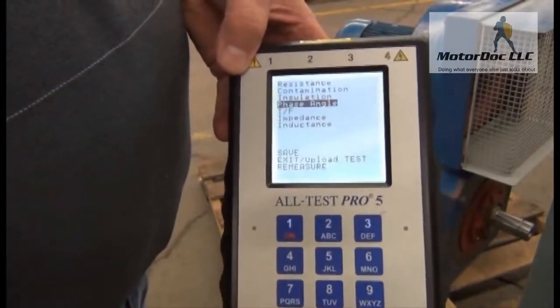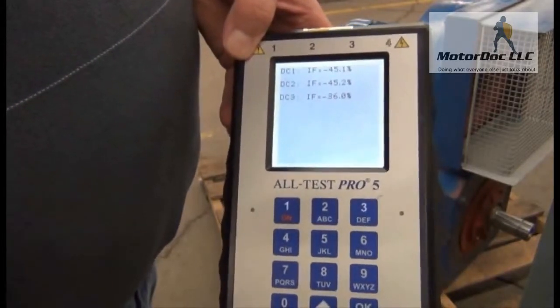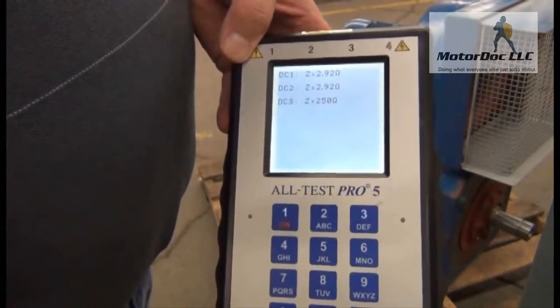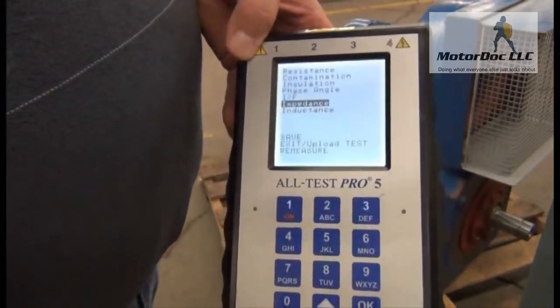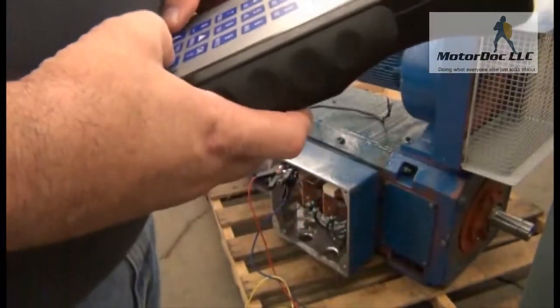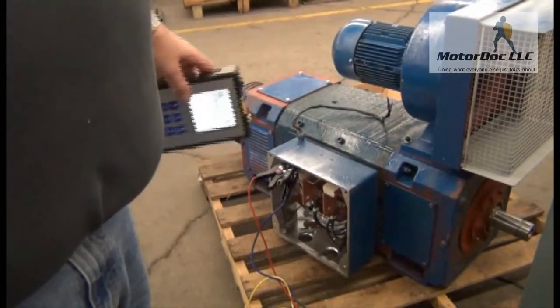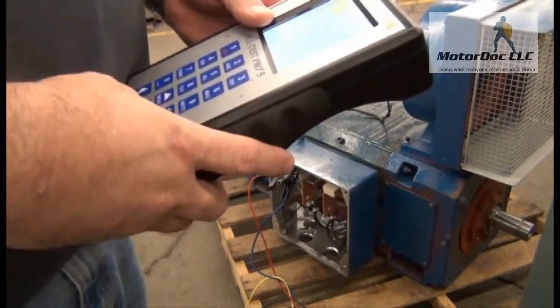Press OK. Same thing with IF. Press OK. Same thing with impedance. Press OK. And same thing with inductance. That's the super secret testing that you can do with the All-Test Pro 5 to check your armature out without having to disassemble the machine. This works on any size DC machine.